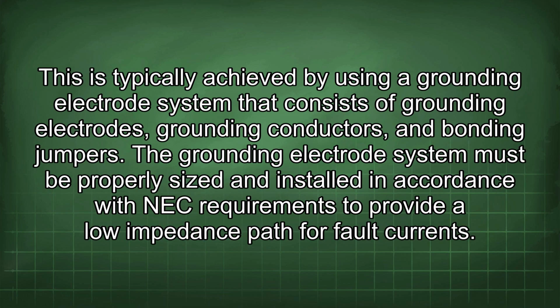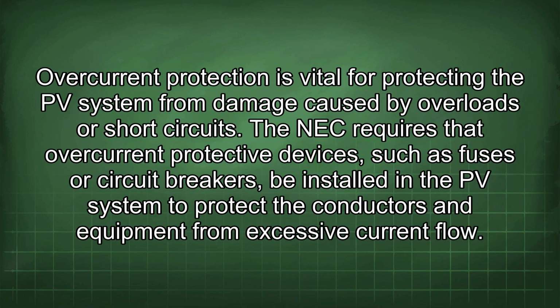This is typically achieved by using a grounding electrode system that consists of grounding electrodes, grounding conductors, and bonding jumpers. The grounding electrode system must be properly sized and installed in accordance with NEC requirements to provide a low impedance path for fault currents. Overcurrent protection is vital for protecting the PV system from damage caused by overloads or short circuits. The NEC requires that overcurrent protective devices, such as fuses or circuit breakers, be installed in the PV system to protect the conductors and equipment from excessive current flow.